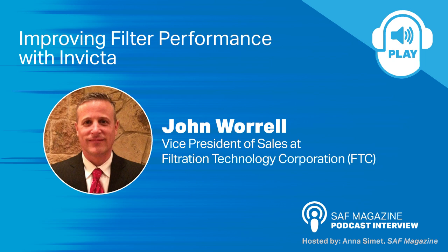So, John, FTC changed the shape of traditional cylinder filters. Why did you guys do that? Well, I think it's first of all important to understand that filter performance can be directly tied to usable surface area. All things being equal, the more usable surface area that you have in a given system, the more dirt a filter will hold, and the higher the efficiency a filter will be at removing a given contaminant size. This can be proven via Darcy's law, which we use to calculate flow through any porous medium. And we know, according to Darcy's law, that dirt holding capacity is indirectly proportional to flux rate or flow per unit area.